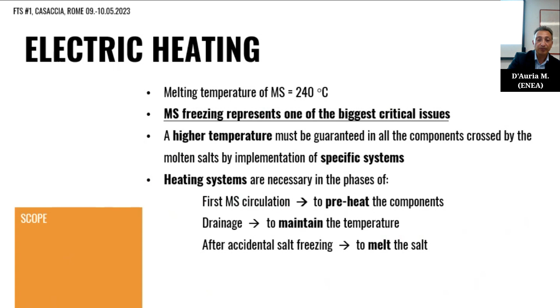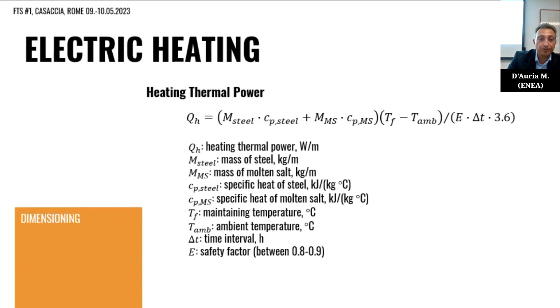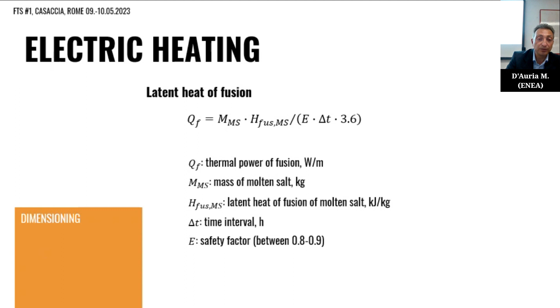For dimensioning an electric heating system, we must consider obviously three different rates, that is heating, maintaining, and supplying the heat of fusion. So for heating thermal power, we must heat the mass of the steel and the mass of the molten salt from ambient temperature to the final temperature. For maintaining thermal power, if we refer to a pipeline, we must compensate the conductive heat loss through the insulation layer. And in the case of freezing, the thermal power is related to the latent heat of fusion of the molten salt.